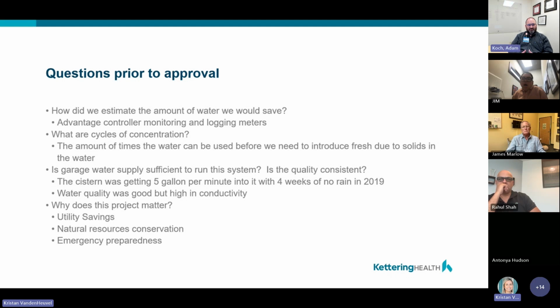Some of the questions we got: how are we estimating the amount of water we would save? We actually monitor our cooling towers and makeup meters through an Advantage controller. We get digital readings and reports, and can go back a year or two and pull that data, so we're able to estimate off of that. That's also how we track cycles of concentration, the amount of time water can be used before we have to reintroduce fresh water into the cooling towers because of solids.